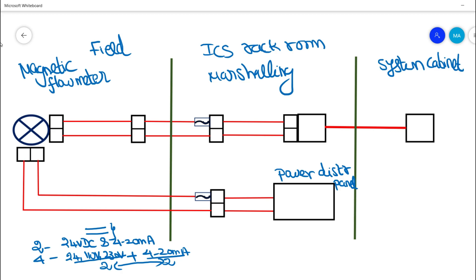This is basically a magnetic flow meter and I would give it a tag number FT-215 — just a random number. This magnetic flow meter has a 4-wire system. One set of wires carries a 230 volt power supply. Depending upon the application we use 230 volt AC, though in some cases 110 volt DC may also be used. So how does this power supply get to the instrument?